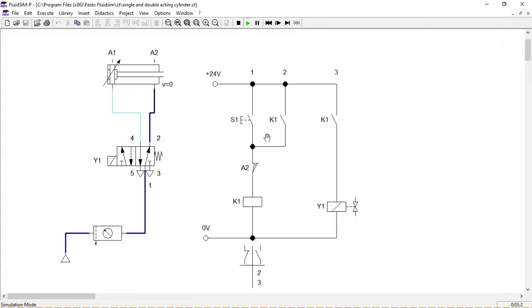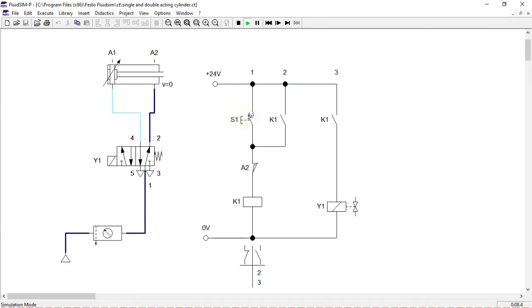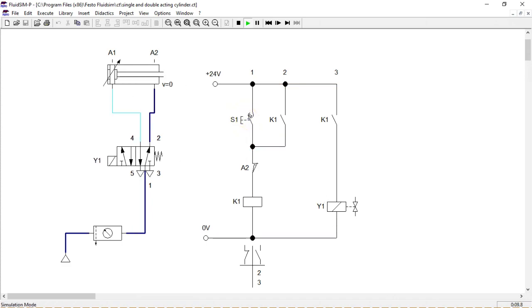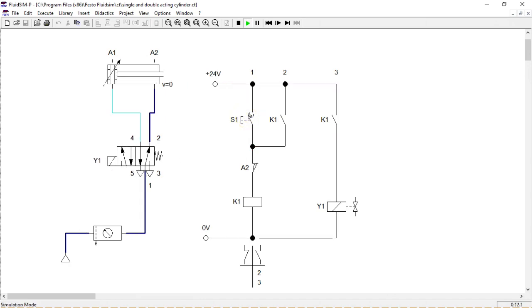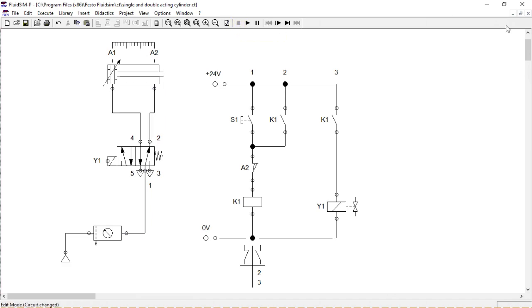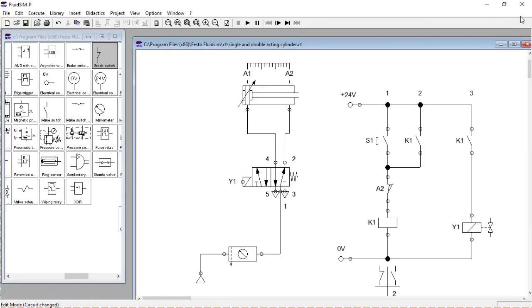When we press S1, the cylinder starts to extend. When it's fully extended, limit switch A2 is activated and becomes open. This will de-energize K1, causing the cylinder to retract.